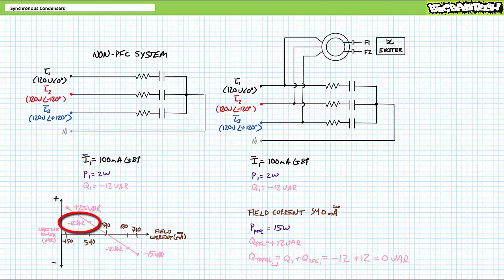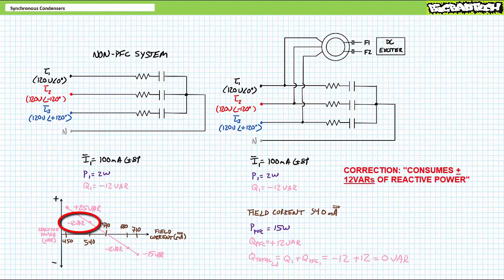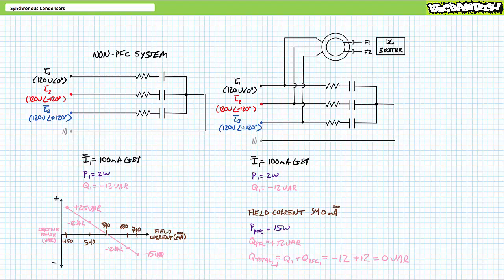When we decrease field current to approximately 540 mA DC and under-excite the rotor, each winding of the synchronous condenser consumes roughly 15 watts of real power for friction, but in this under-excited state also consumes positive 12 VARs of reactive power — equal in magnitude and of opposite polarity to the load. Given current to the load leads and current to the synchronous condenser lags, source current (the summation of load and synchronous condenser current) appears in phase with supply voltage. The equal and opposite reactive powers cancel such that each phase only needs to supply 2 watts to the load and 15 watts to the synchronous condenser for a total of 17 watts. Any reactive power is cyclically exchanged between the load and the synchronous condenser at the point of use, and the source stays out of it.